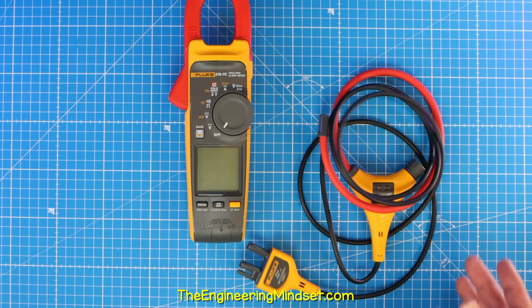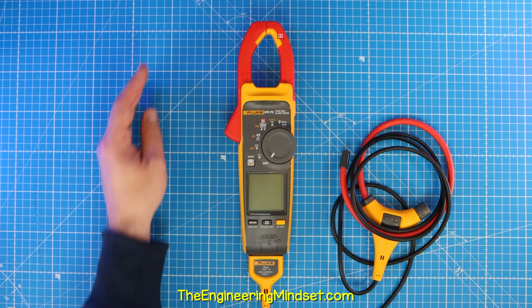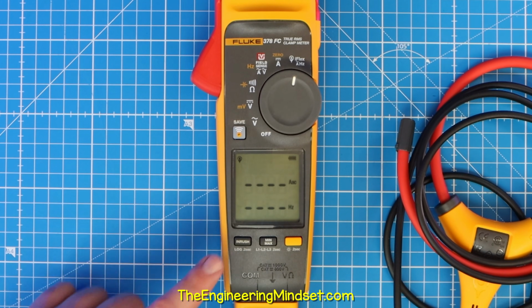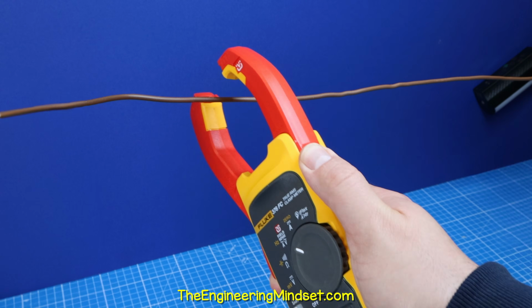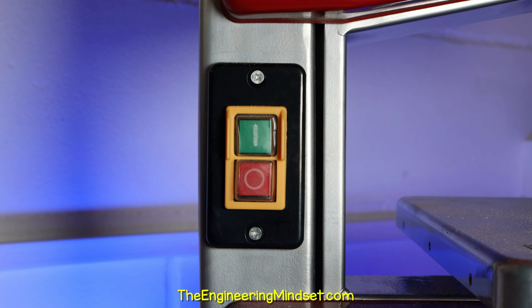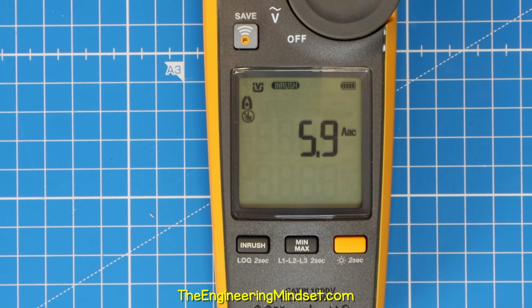If you have a flex cable, you can use this too. Just select the iFlex function and press the Inrush button. On manual range, select the appropriate AC current range and cycle through the options for inrush current. Then clamp around the wire, and when safe to do so, turn on the device to capture the inrush spike.